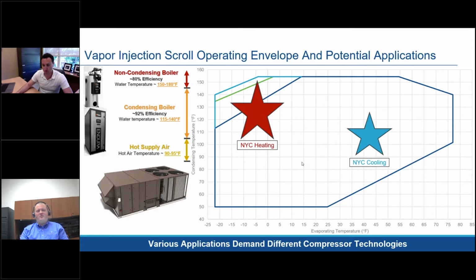They're both high pressure refrigerants, and part of the reason we use high pressure refrigerants is that if you start using R134A or low pressure refrigerants, which are typically used in heat recovery chillers, those chillers have higher evap temperatures. If you use a low pressure refrigerant, a lot of times we run into a problem where there's not enough force to keep the floating seal sealed with the muffler plate in the compressor. So you're not actually going to be able to run at what I call high compression ratio conditions, which is the top left. I'll have another slide coming up to explain that.